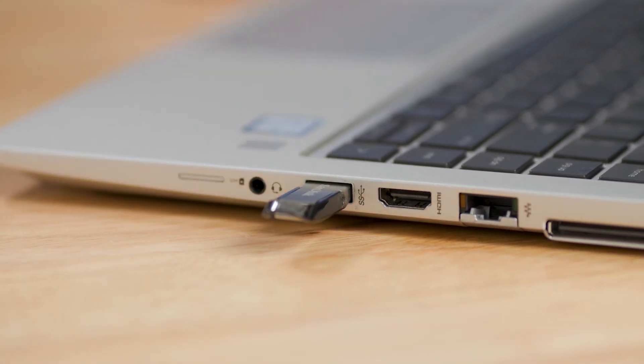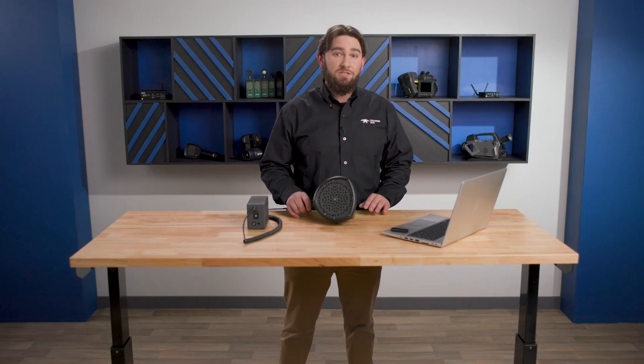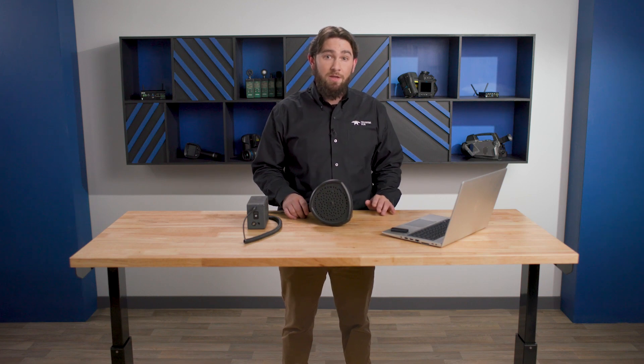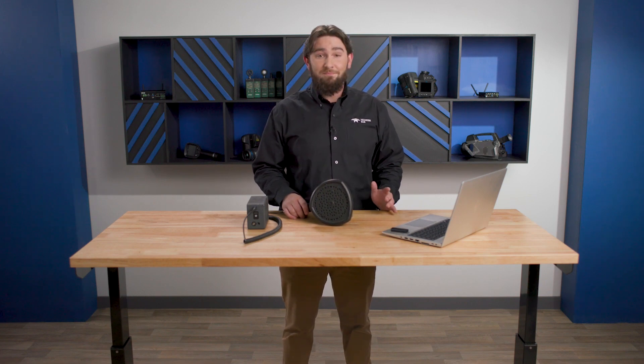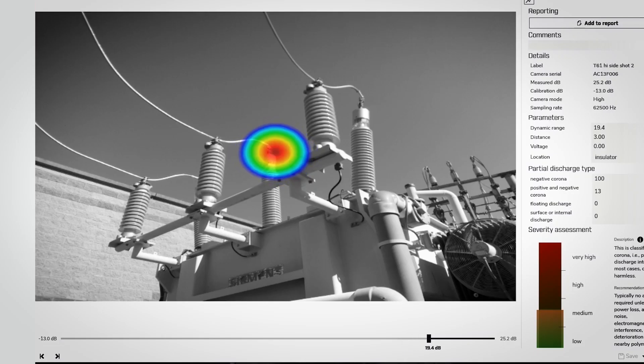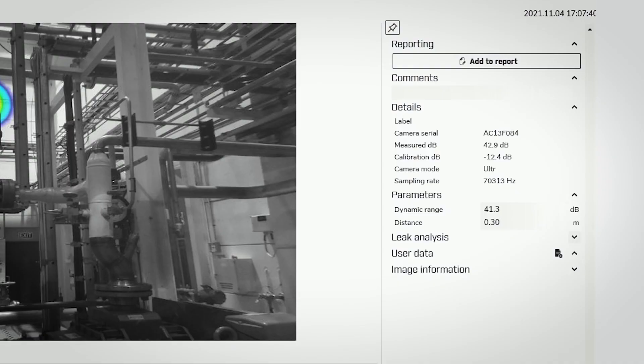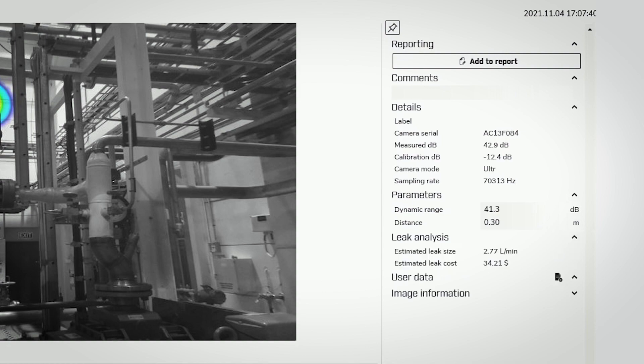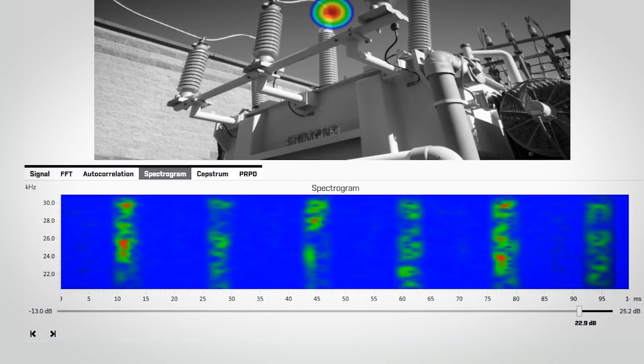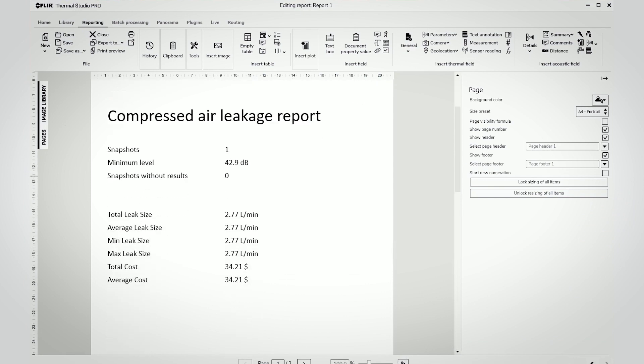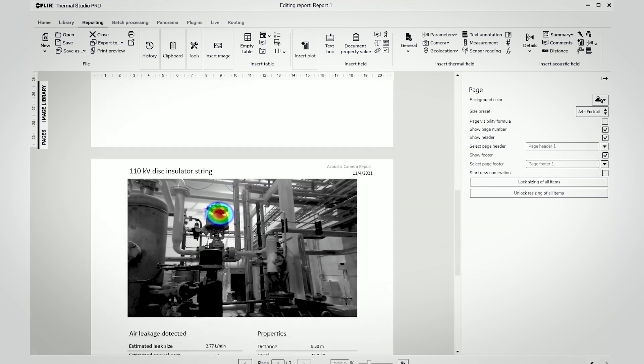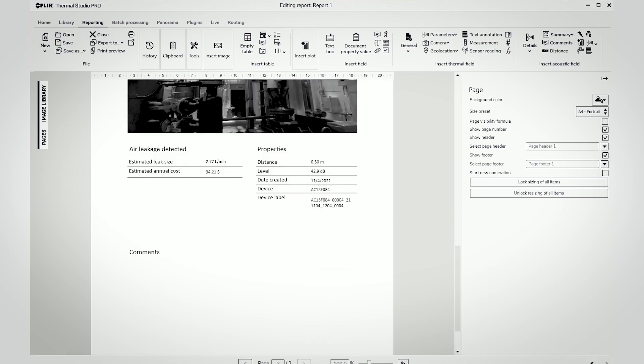You just transfer images to a computer running FLIR Thermal Studio Pro software. When paired with the free Acoustic Viewer plugin that comes with your SI124, FLIR Thermal Studio Pro is really the best resource for analysis and reporting. This feature-rich plugin allows SI124 users to edit images and review critical data, including analysis tools such as estimated leak size and annual leak costs, as well as data from the waveform and frequency content. You'll use these to quickly calculate the size of a compressed air or vacuum leak and determine the annual energy savings once the leak is repaired.